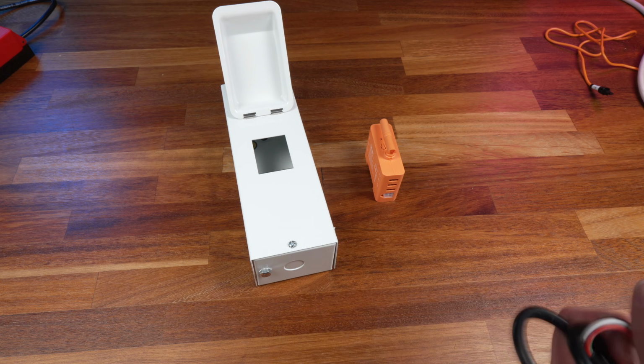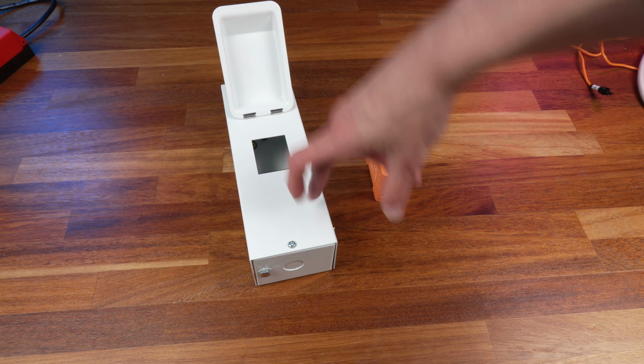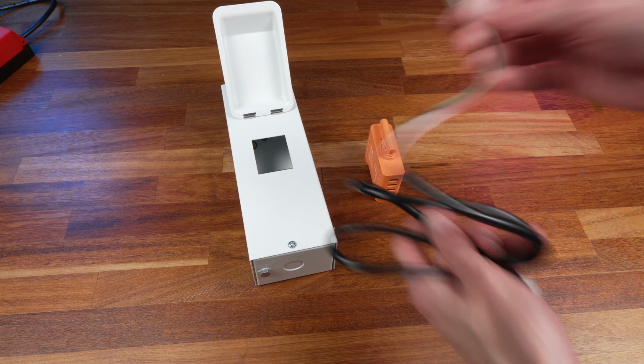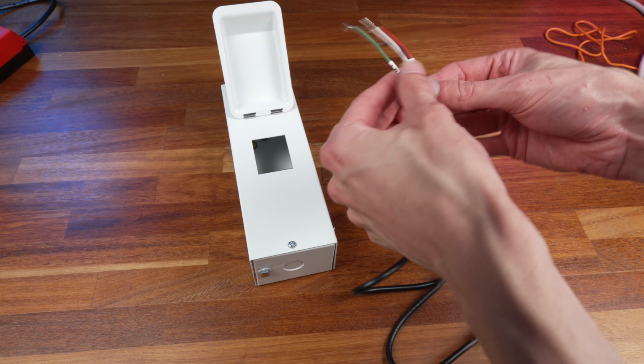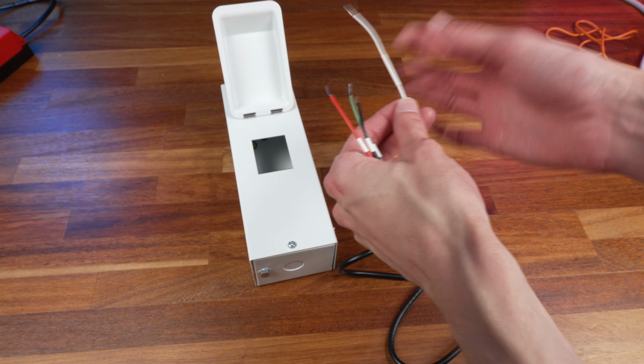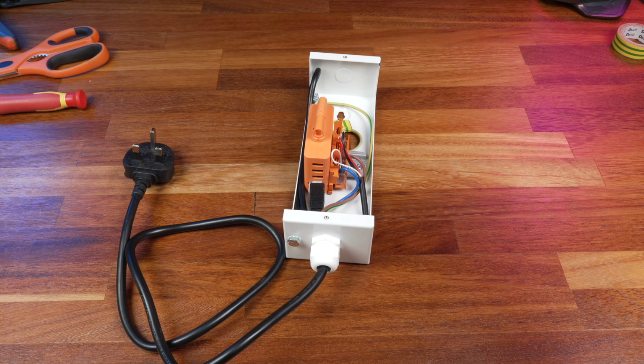So what I'm going to do, instead of just wiring these directly in, I'll wire a mains flex into this, where I can then connect the earth into the metal casing here, and I'll put some terminal blocks in where I'll connect this cable here up to that flex to connect the 3 lives to the live and the neutral to the neutral. And there we go. So it's now all assembled in the enclosure and ready to be installed.